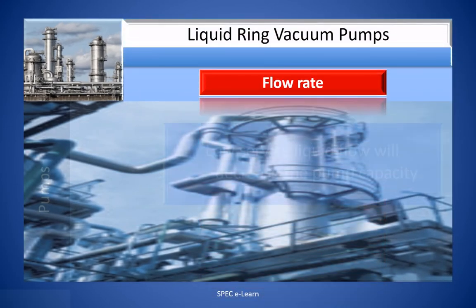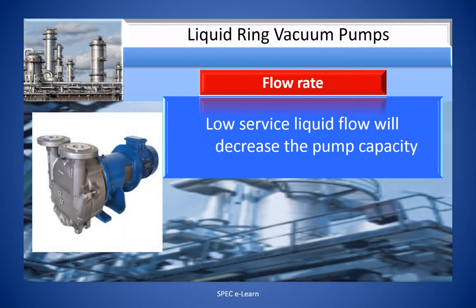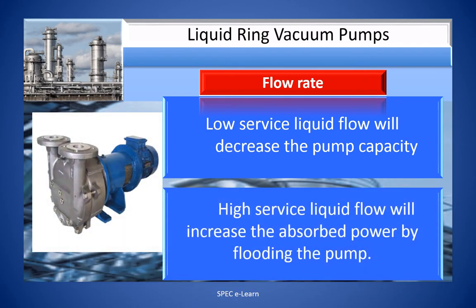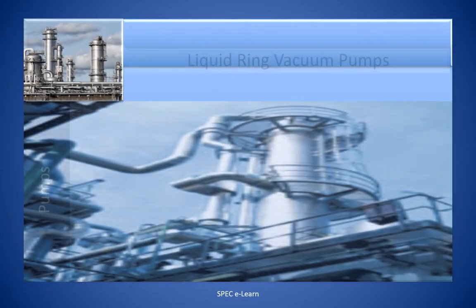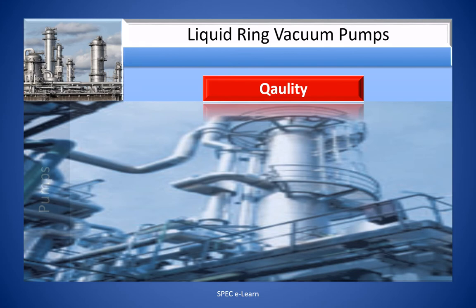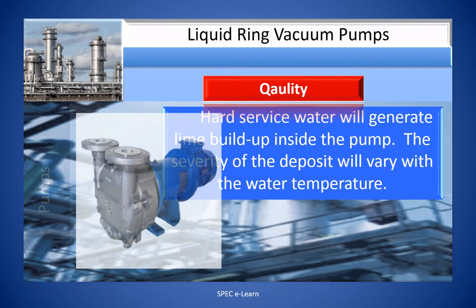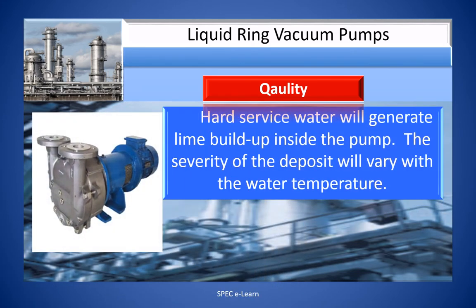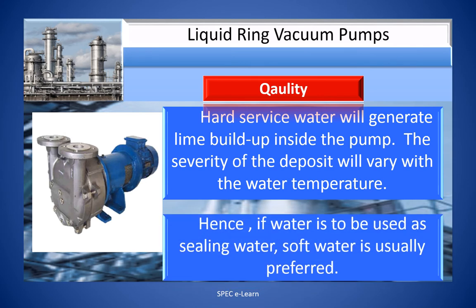Regarding flow rate: low service liquid flow will decrease the pump capacity, while high service liquid flow will increase the absorbed power by flooding the pump. Regarding quality of service water: hard service water will generate lime buildup inside the pump. The severity of the deposit will vary with the water temperature; hence, soft water is usually preferred.